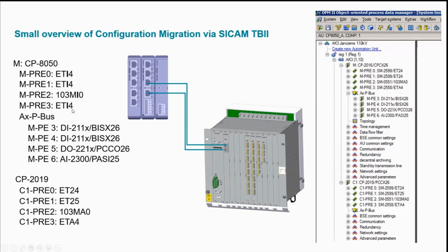Protocol 3, same thing. Now, we know that the I/O modules are not connected directly with the master firmware of the CP8050, but are connected to the extended processing. So we will need one instance of external extended processing in this CP8050. So we will call it C1. This is the first extended processing unit or virtual CPU. And there we will connect one 8000 rack, the first one.